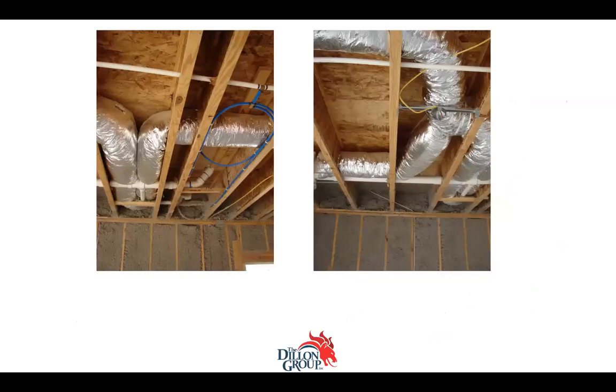It sure would be nice if Manual D had a little, and I've talked to Wes Davis and David Bixby at ACCA about this, there's 100,000 different ways to do a duct system per Manual D. And for instance, I think one of my pet peeves is the teeny tiny plenums, because evidently duct board's made out of gold. So we put these teeny tiny supply plenums on there and have takeoffs immediately after the piece of equipment. But as far as the black and white of Manual D, 18 inches from the end plate is the only prohibited area. Everything else could conceivably be designed per Manual D.